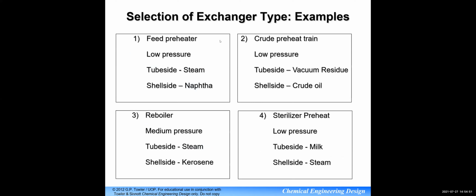But I would like to point out that the heat exchanger itself can exchange so many fluids, so many gases. So you can have, like this one, a feed preheater. It needs a low pressure, but in the tube side it has steam, and in the shell side it's naphtha. So you can see here it is a preheater, and we can see the hot stream is in the tube side as steam, and the naphtha stream is being heated by the steam.